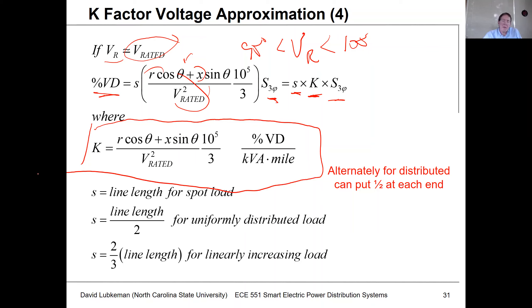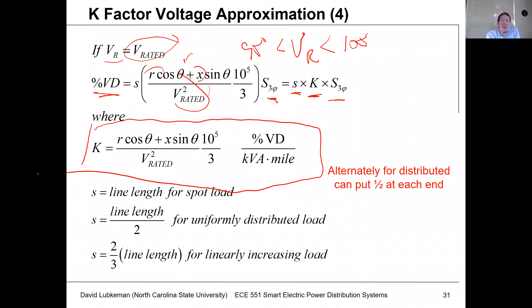The K term indicates by how much the voltage drop changes as the equivalent line length S increases when the circuit is loaded up. In the simple case where all the load is at the end of the feeder, this is referred to as a spot load situation.